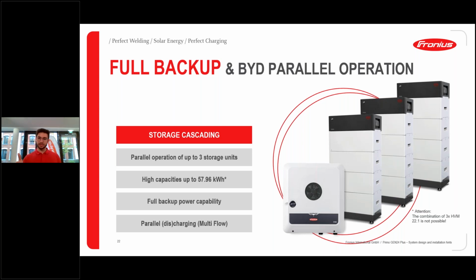And this is also one thing I want to explain in this slide. We can mount up to 3 towers of those batteries. So there is basically no restriction other than one. The maximum capacity that BYD can deliver is 3 towers with 8 modules stacked on each other. So this would be 22.1 kilowatt hours times 3. Unfortunately, that's a little bit too much for Fronius. So we have a limitation of 3 towers with 7 modules. So this would be 57.96 kilowatt hours. That's the maximum capacity we can connect to our components. But I think this is really a high capacity on this product and should be sufficient for mostly any residential usage. So this can be connected here, and it's necessary for a full backup.